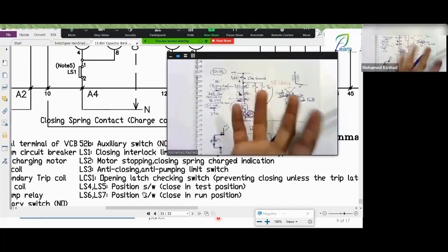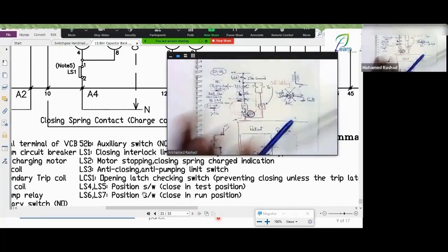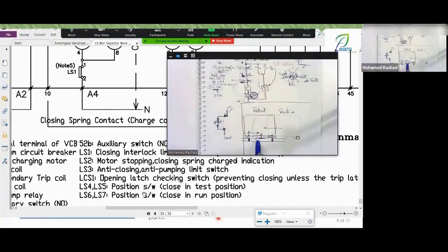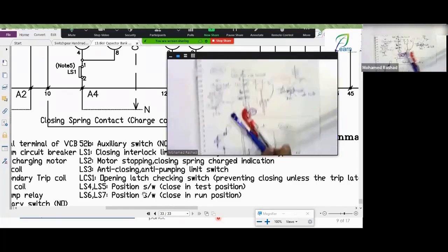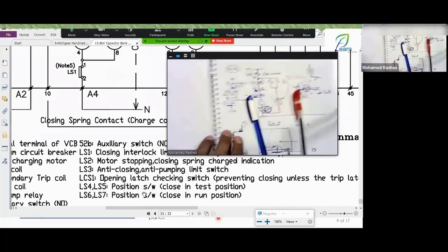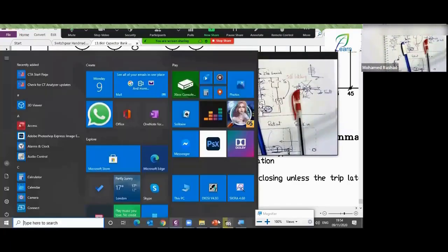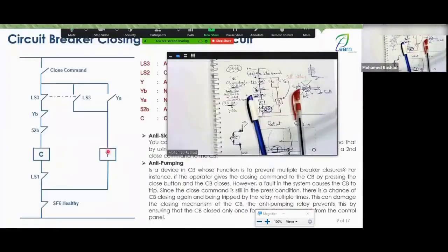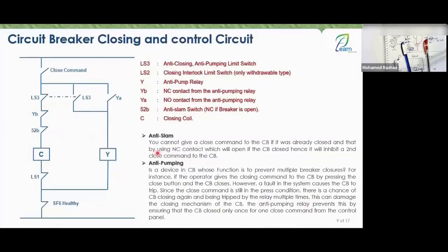Will the breaker mechanically close, engineer? No, it's impossible for it to close at all. Why? Because mechanically, it considers the mechanical interlock process. But electrically, it would have connected DC to the closing coil, burning the closing coil of the circuit breaker. Is that clear, engineer? Great. Now let me get back to you. Are you tired of me yet? So I'll get back to you again.